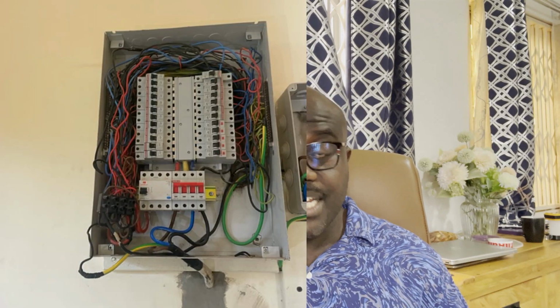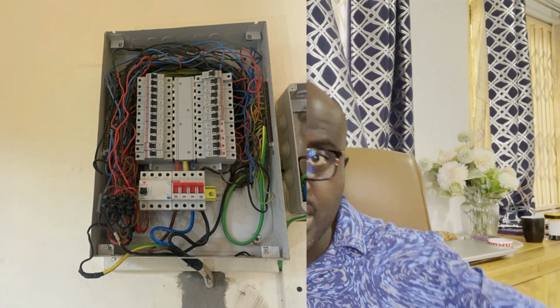And when I asked him, he said, oh, because they were short of cables. Well, no, that's not good enough. Keep the color codes correct, because if somebody comes later on, it may not be this electrician but another electrician, and they look at it, oh, this is earth, and then they touch it by mistake or do something, or wire it by mistake. That's where you could have significant problems, an explosion, a short circuit. Somebody could have a fatal injury. What have you? Keep it correct as industry standard. Very, very dangerous. I condemn that straight away.